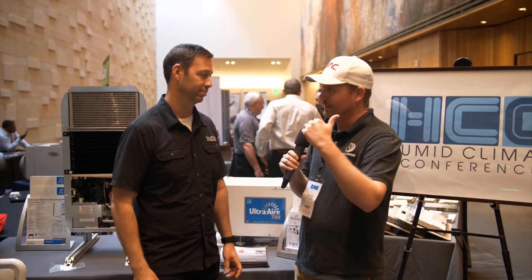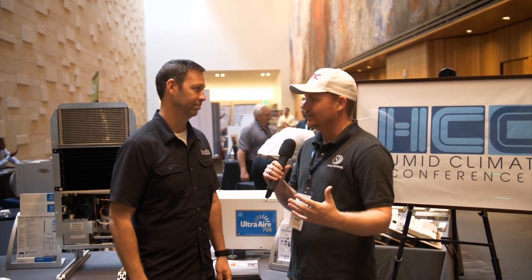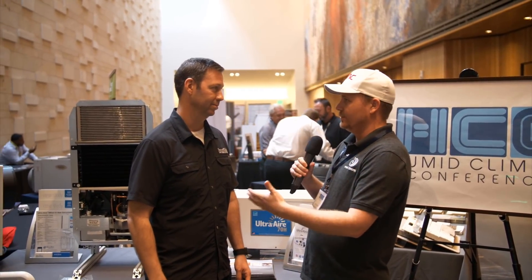This is exactly what we've talked about a little on the podcast. When you start to think about sensible heat ratios and actually look at those ratings, you begin to realize that some equipment matches just aren't going to cut it. Even when you match the equipment perfectly, you have this balance — this dance — between sensible and latent. So you obviously started using dehumidification regularly.